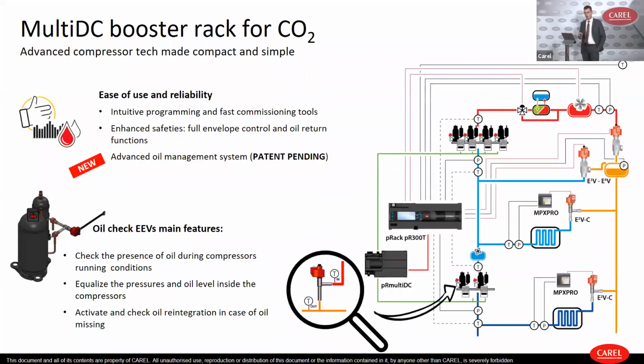Let's have a very quick overview of the system that you can see on the right. So pRack, the transcritical version, is managing more or less all the needs of the unit, except for the DC drivers and the electronic expansion valve that we use for the oil check, which is in charge of the PR multi-DC controller. If we speak about the oil check and pressure and oil level balancing valves, these devices are fitted on the side of the compressor with an inlet temperature probe and outlet temperature probe in order to check if there is oil inside the compressor, and if not, activate the oil refill from the oil reserve.